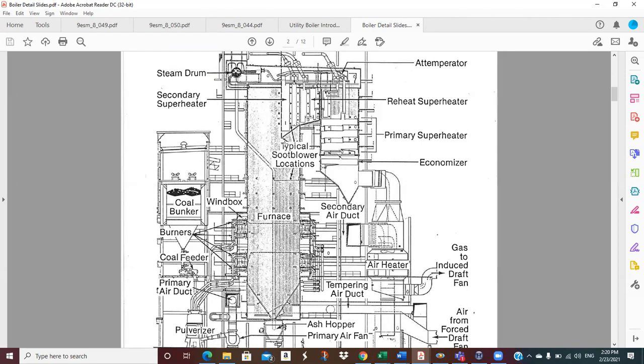And actually, you can remove ash with acoustic horns. There are some boilers that have big horns. Like twice a day, the vibration from the horns knocks the ash off of the tube bundles. Now, if you've got a house that's real close to the power plant, you're probably not real fond of the acoustic horns. You'd probably rather them blow some water or some low pressure steam or something to knock that stuff off. And they do have to take that into consideration, but acoustic horns are one possibility for soot blowing.